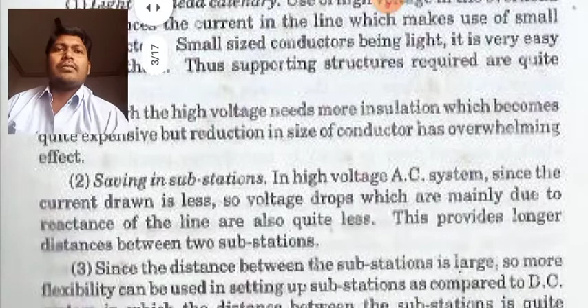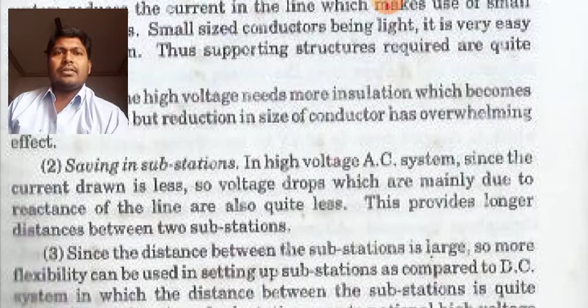So saving in substation. In high voltage AC system, since current is less, the voltage drops, which are mainly due to reactance of the line, are also quite less. This provides longer distance between two substations. Since the distance between the substations is large, more flexibility can be used in setting up substations as compared to DC system, in which the distance between the substations is quite small.